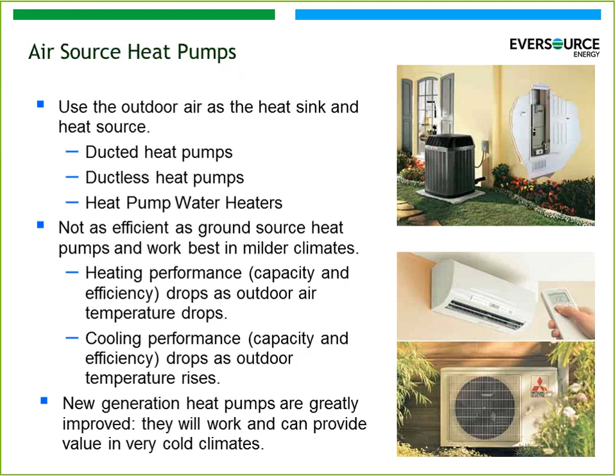I mentioned new generation cold climate heat pumps, and here's a chart from a leading manufacturer of ductless heat pumps. Essentially, the blue line that you see on the bottom right is the heating capacity of, I'll just call it an older generation type of heat pump. You can see at around 14-degree outdoor temperature, the heat pump can only provide about 60% of its rated capacity. Typically, with older generation heat pumps, oftentimes you wouldn't even think about using them if it was below 20 degrees. You would resort to some type of backup electric resistance or some other type of backup system.